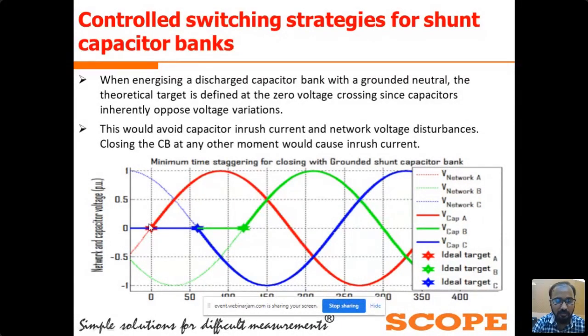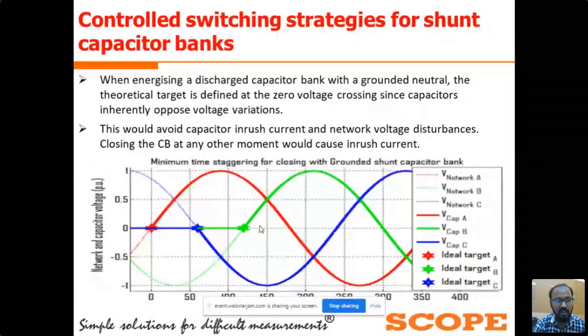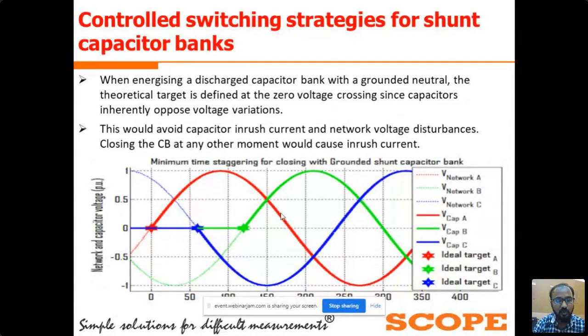So if we execute the command by taking the reference of the R phase only, we can set the target points, that is the 0 degree, 60 degree, and 120 degree. At these electrical points, the system voltage for all three phases is near the 0 point. So if we close the circuit breaker near this system voltage 0 point, the inrush current will be minimum for the closing of the capacitor bank. So basically, this is the strategy that we are using for controlled switching of capacitor bank applications.